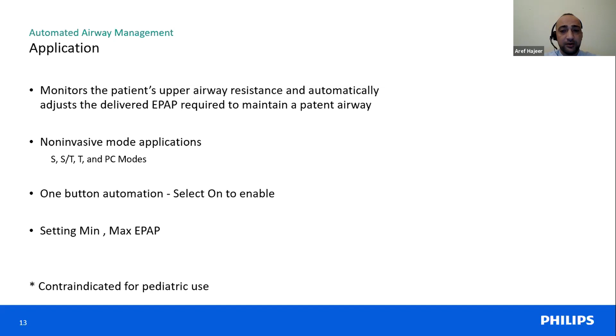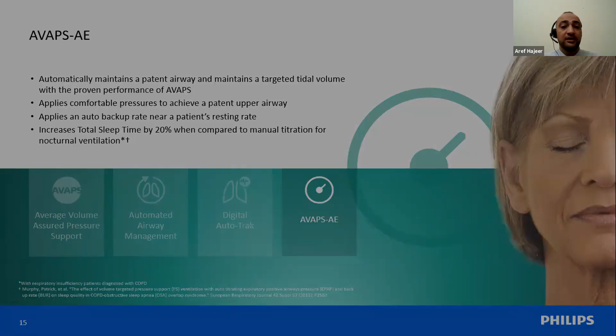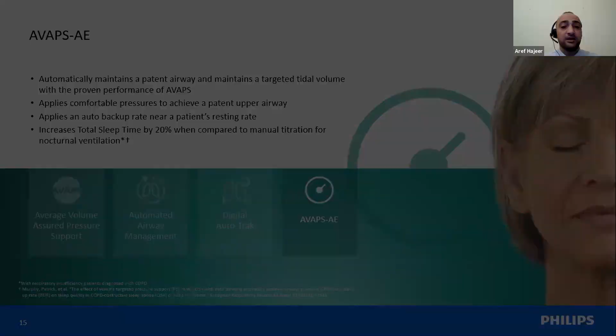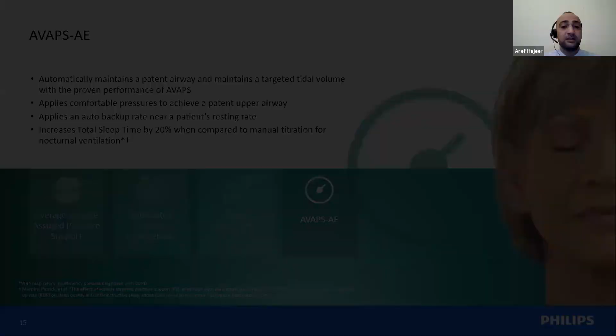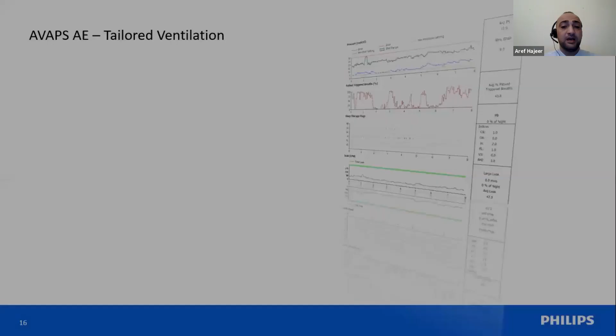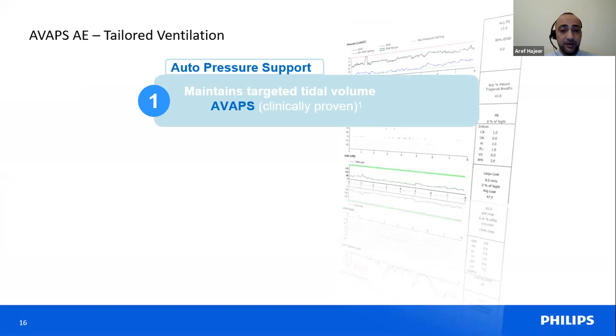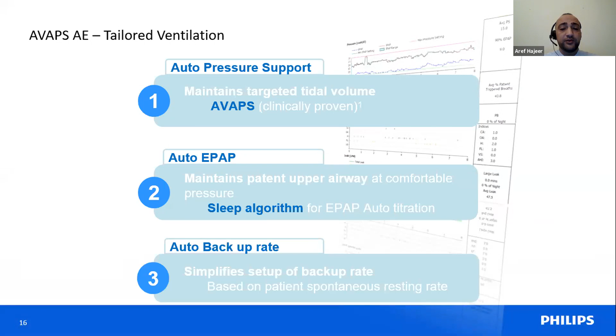Last but not least, AVAPS-AE as a mode. Think about if we can combine these two features, the AVAPS and the automated airway management, in one mode of non-invasive ventilation. And this is what we did in Philips, and this is how we created the AVAPS-AE mode. It has three main features: the auto pressure support, by using the AVAPS, which maintains the target tidal volume for the patient. The second thing, the auto EPAP, we added in the same mode, so it will help to maintain the patient's airway open.